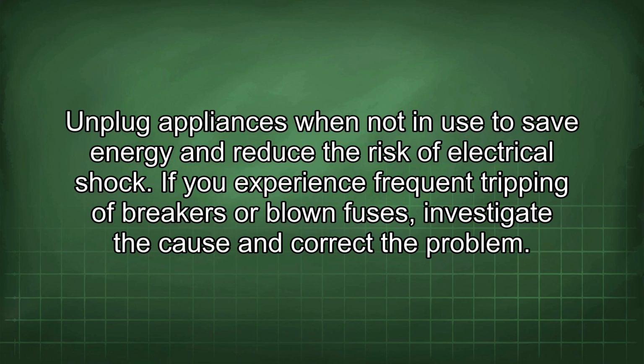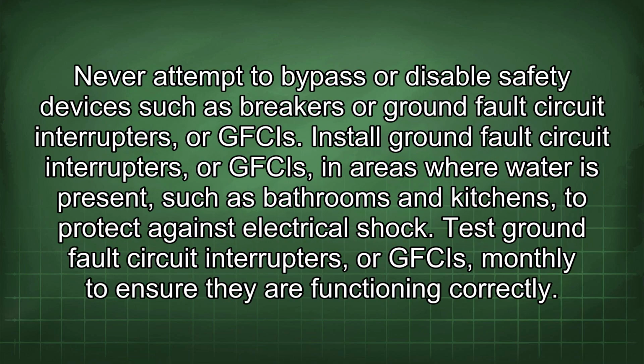If you experience frequent tripping of breakers or blown fuses, investigate the cause and correct the problem. Never attempt to bypass or disable safety devices such as breakers or ground fault circuit interrupters, or GFCIs. Install GFCIs in areas where water is present, such as bathrooms and kitchens, to protect against electrical shock. Test GFCIs monthly to ensure they are functioning correctly.